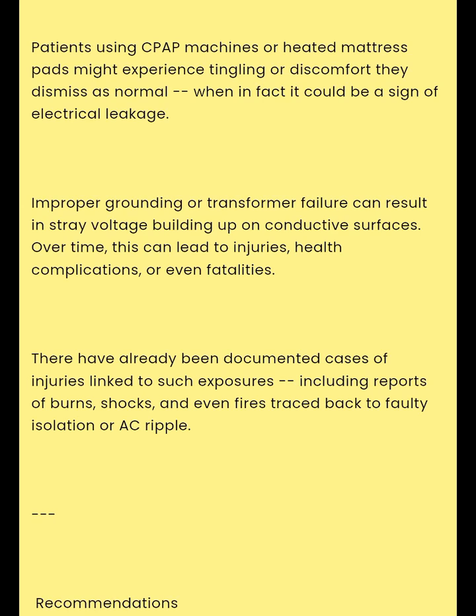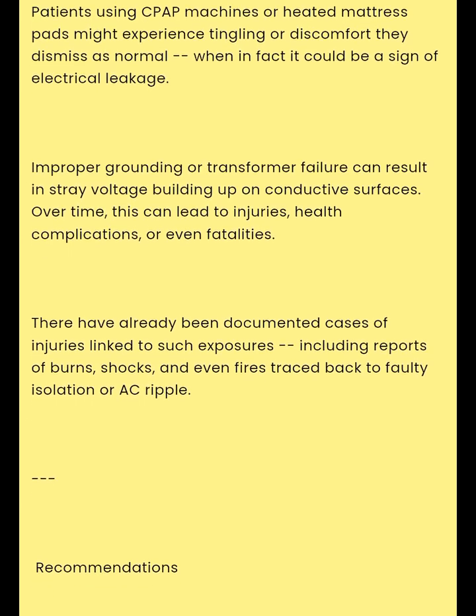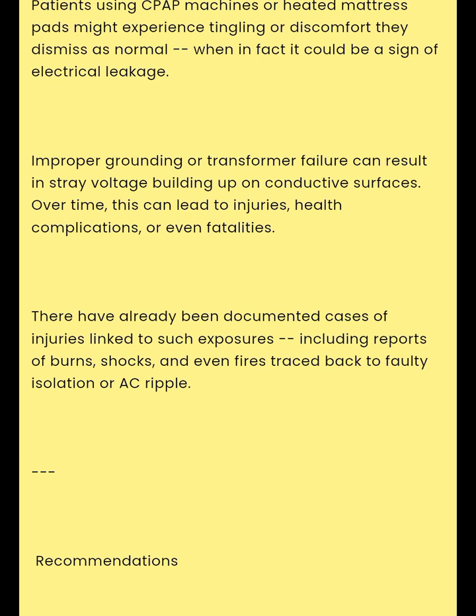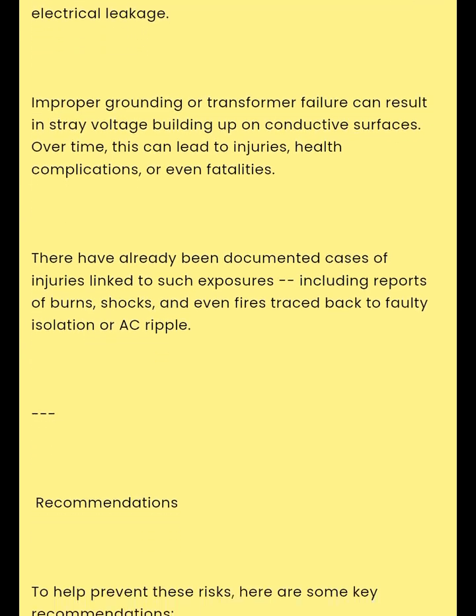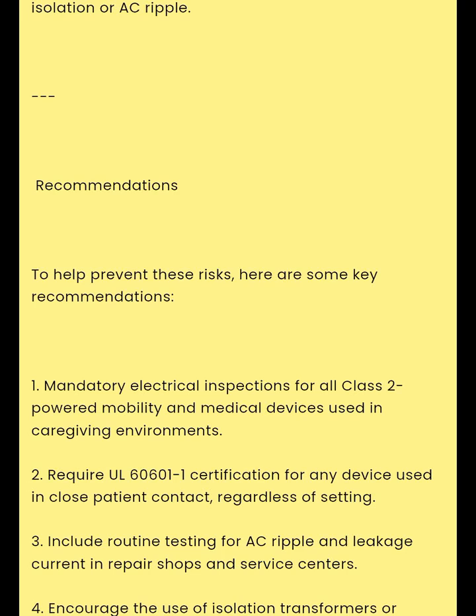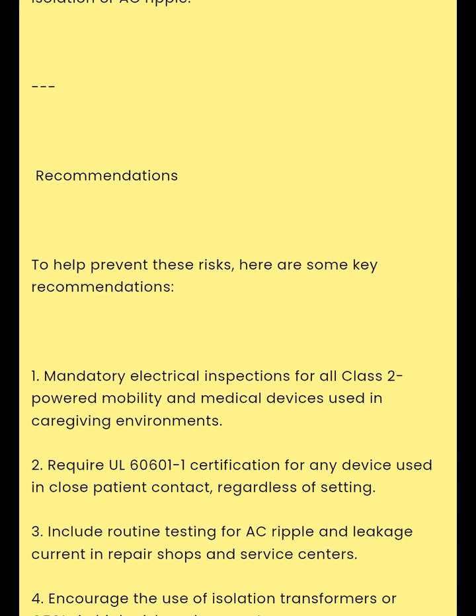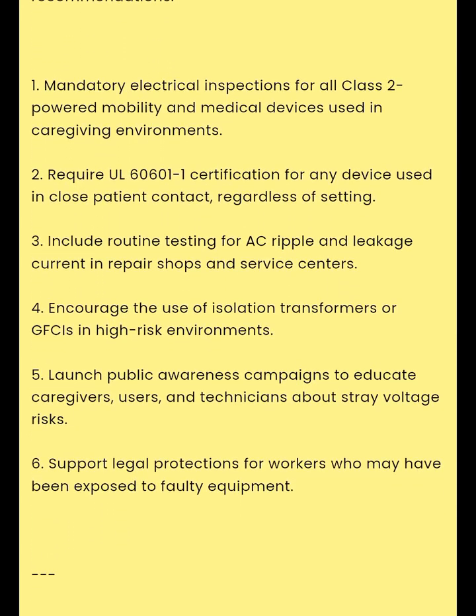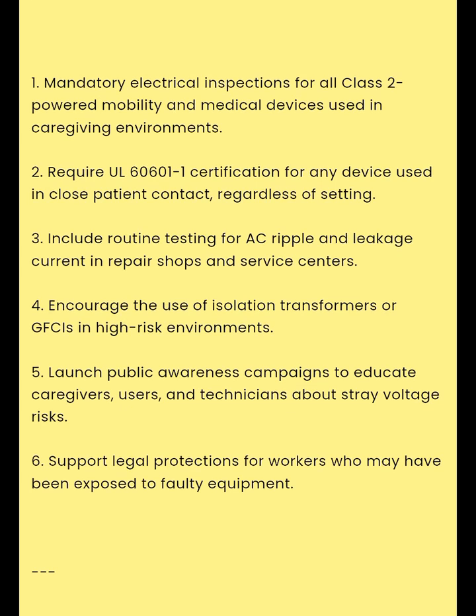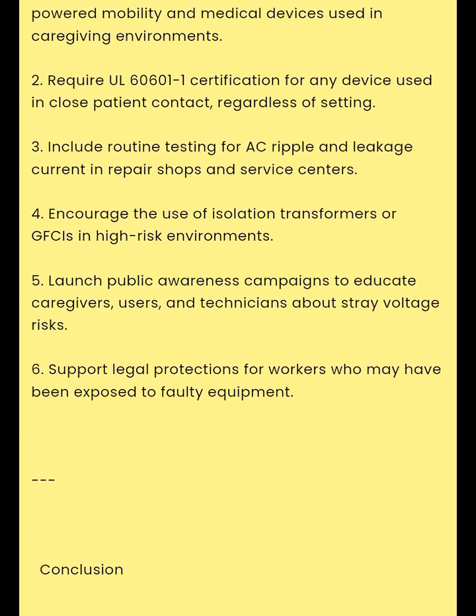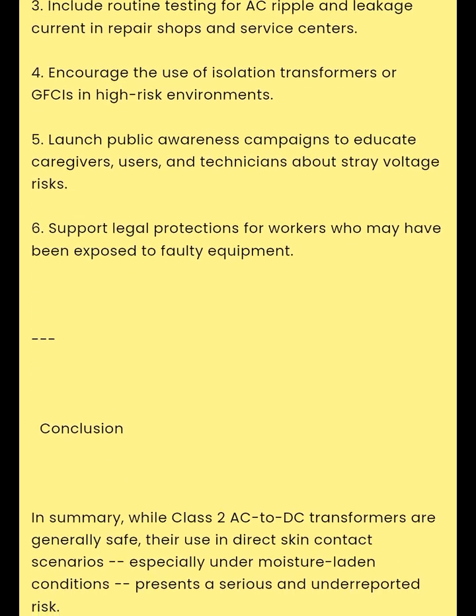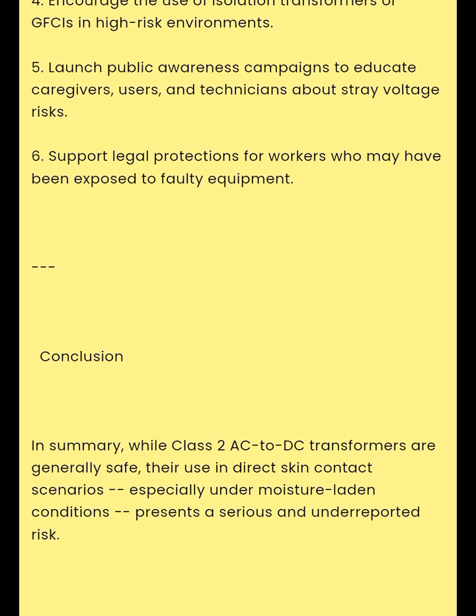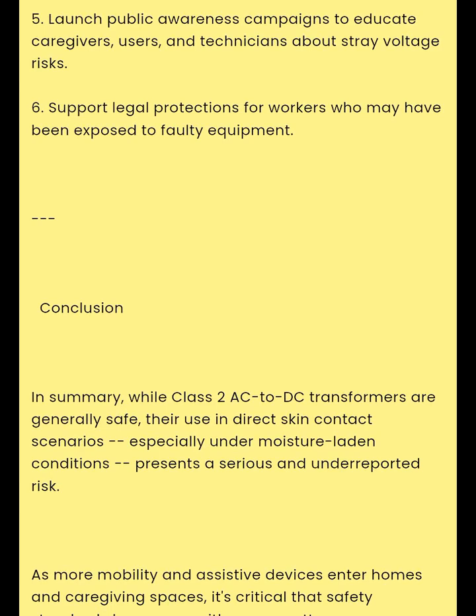There have already been documented cases of injuries linked to such exposures, including reports of burns, shocks, and even fires traced back to faulty isolation, or AC ripple. Recommendations. To help prevent these risks, here are some key recommendations. 1. Mandatory electrical inspections for all Class II powered mobility and medical devices used in caregiving environments. 2. Require UL 60601-1 certification for any device used in close patient contact, regardless of setting. 3. Include routine testing for AC ripple and leakage current in repair shops and service centers. 4. Encourage the use of isolation transformers, or GFCIs, in high-risk environments. 5. Launch public awareness campaigns to educate caregivers, users, and technicians about stray voltage risks. 6. Support legal protections for workers who may have been exposed to faulty equipment.